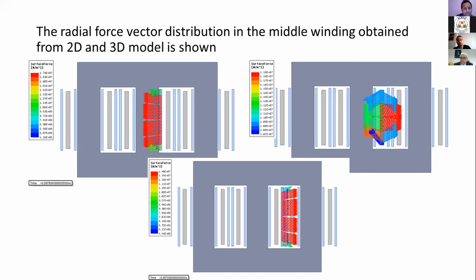Yes, maybe you are right. Firstly, I thank you for your attention and your question, Mr. Dawood. In a normal two-winding transformer, it is like you said. Normally the force direction for the LV winding is toward the core side, and the direction for the high voltage winding is toward the tank side. But as you say, maybe the distance between the windings causes this direction, or in a three-winding transformer, maybe we have this direction.